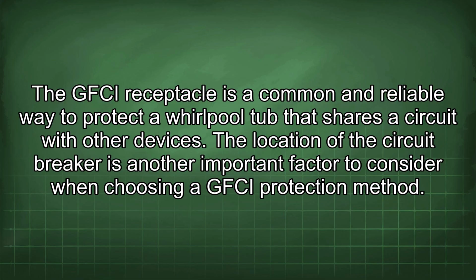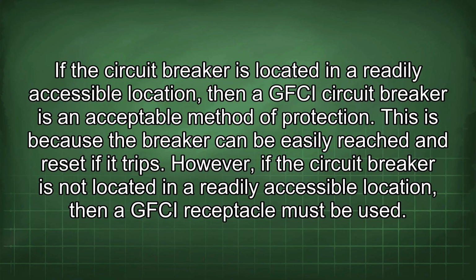The GFCI receptacle is a common and reliable way to protect a whirlpool tub that shares a circuit with other devices. The location of the circuit breaker is another important factor to consider when choosing a GFCI protection method. If the circuit breaker is located in a readily accessible location, then a GFCI circuit breaker is an acceptable method of protection. This is because the breaker can be easily reached and reset if it trips.